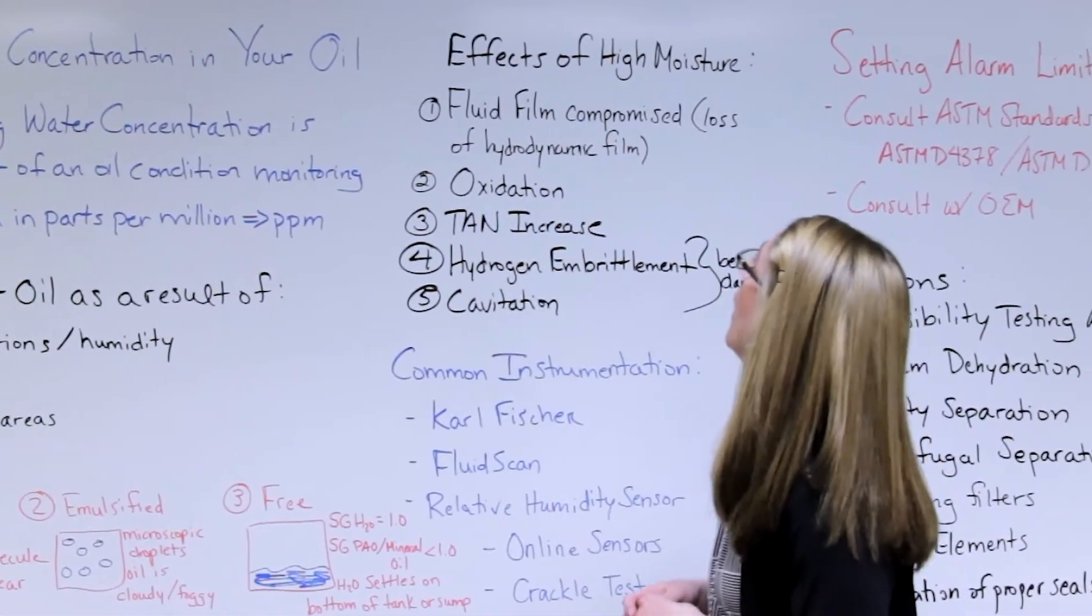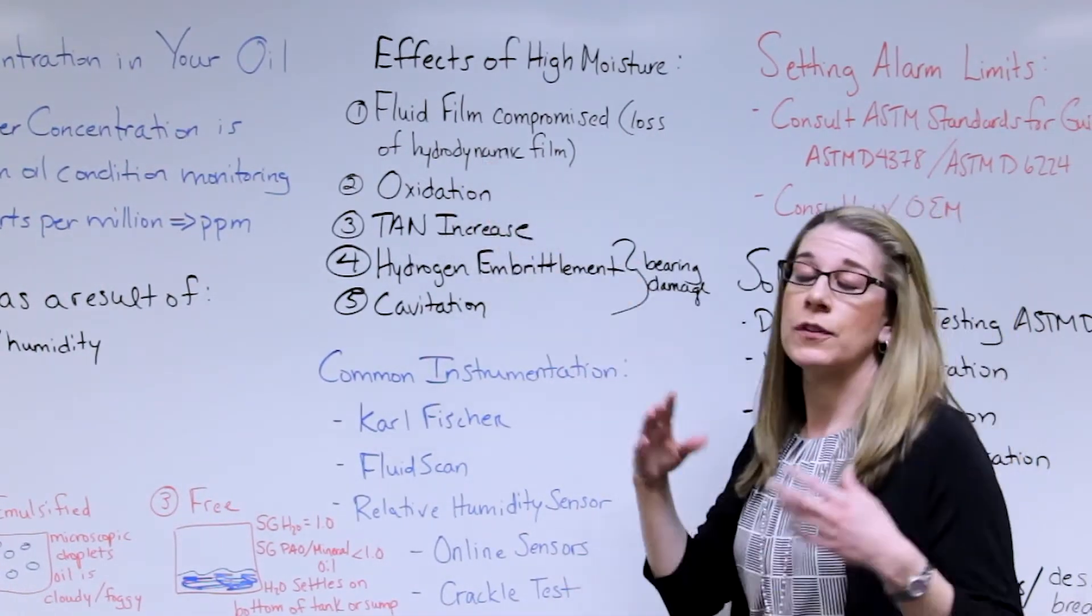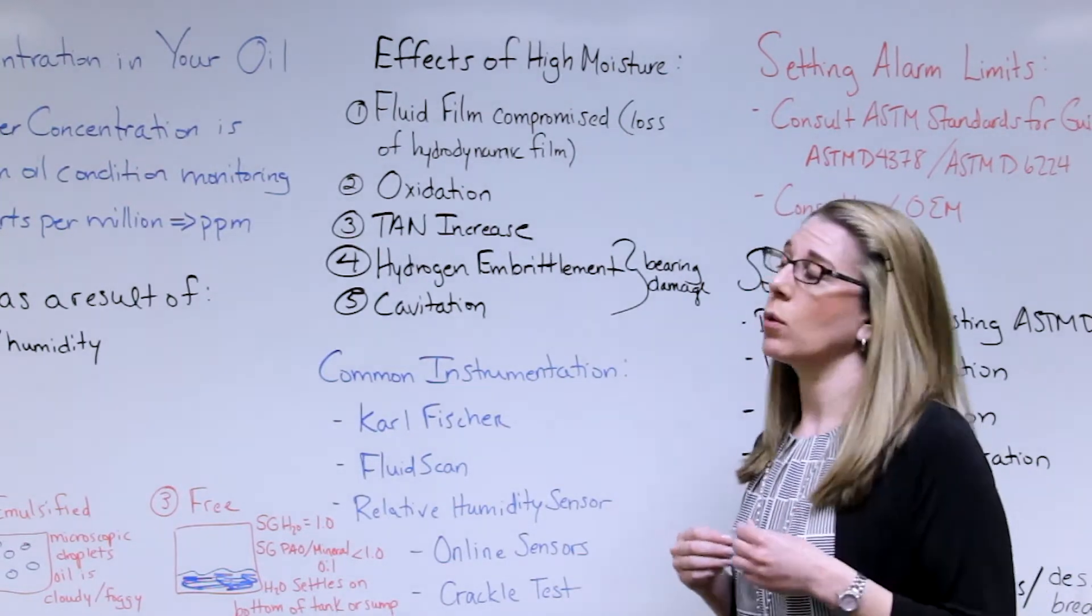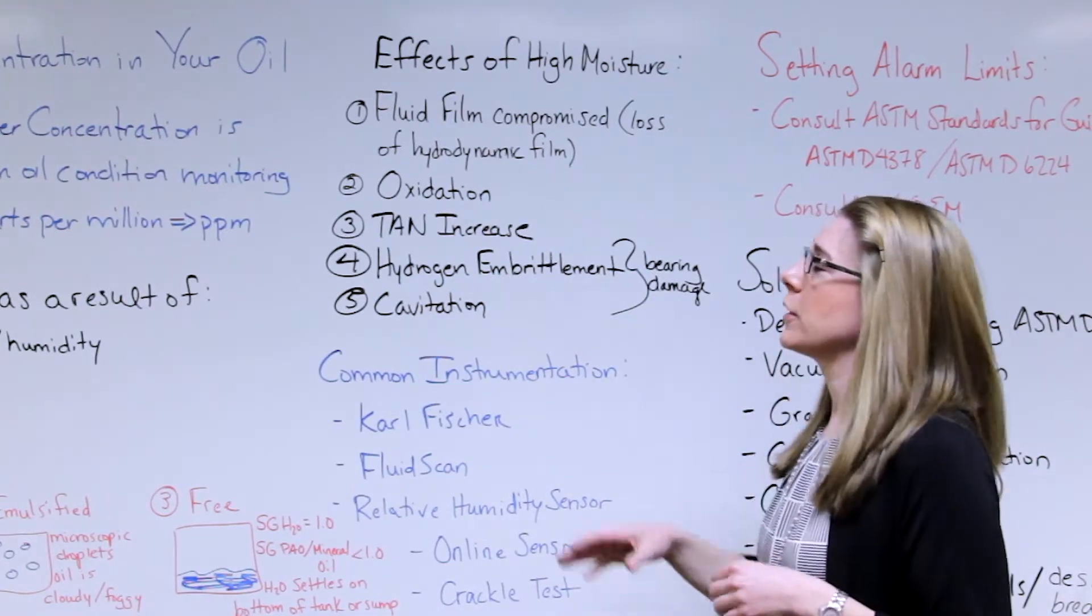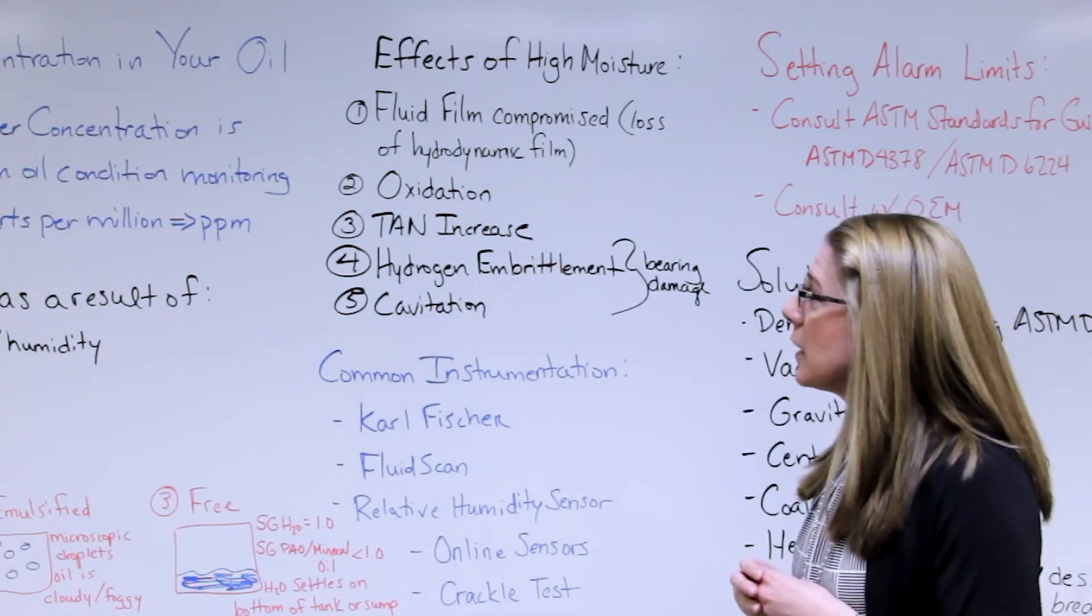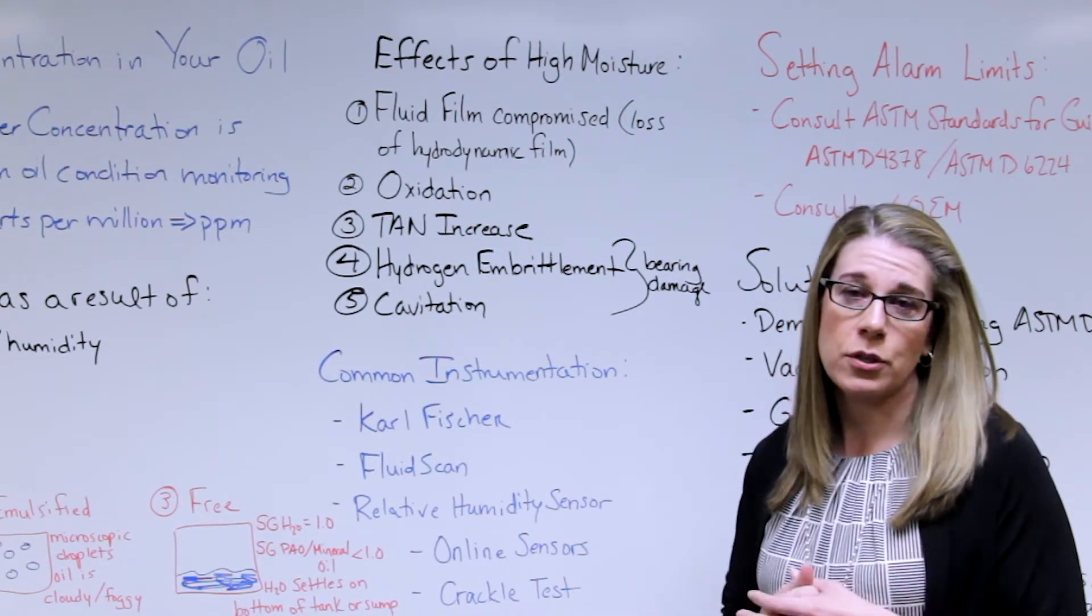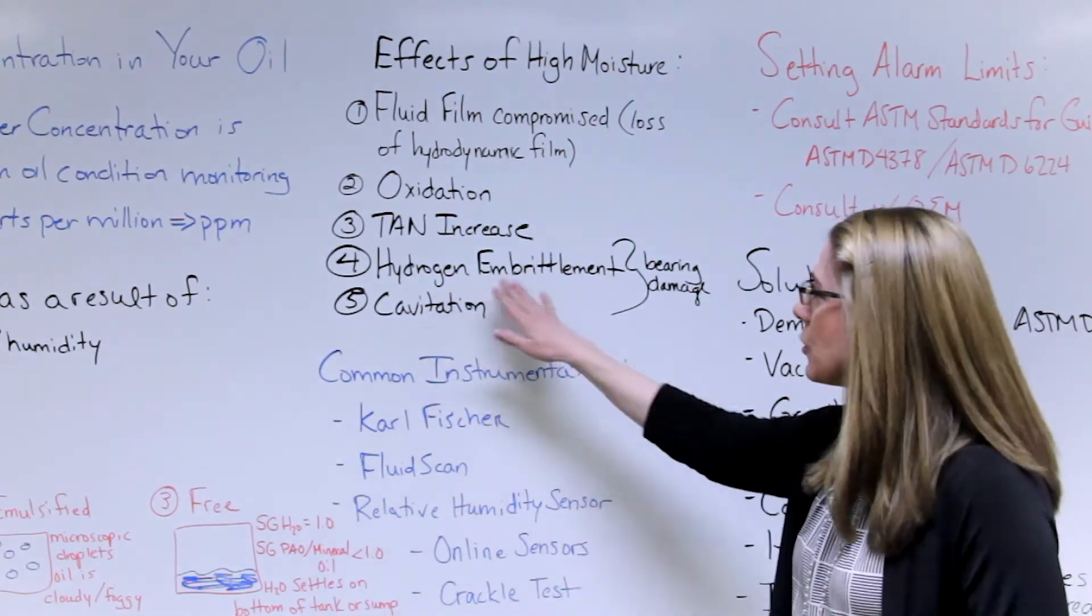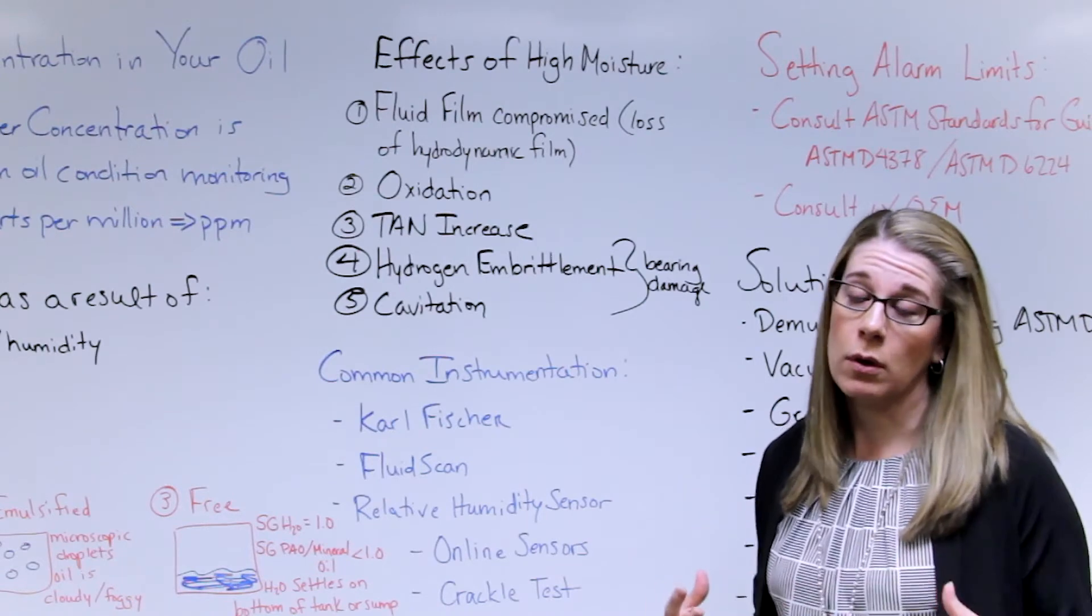What are the effects of high moisture? What can this actually do to your oil? First of all, viscosity is one of the most important things when choosing the right oil. Fluid film is automatically compromised when we have excessive water concentration. That hydrodynamic film is being disrupted, and we also have oxidation and a TAN increase that will occur with excessive water concentration. These last two have to do with bearing damage. We can have hydrogen embrittlement and cavitation occurring as a result of high moisture.